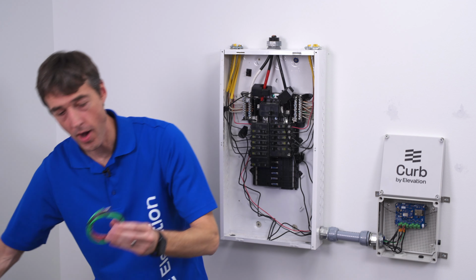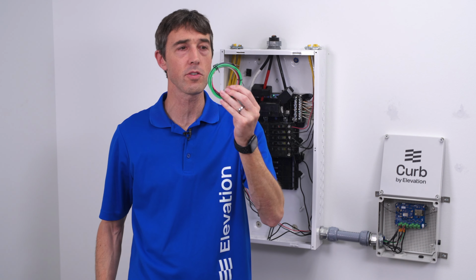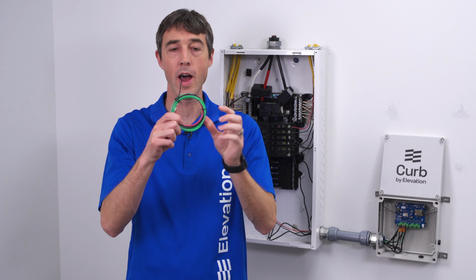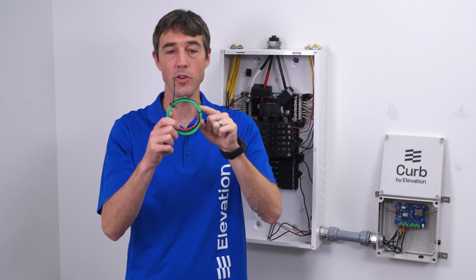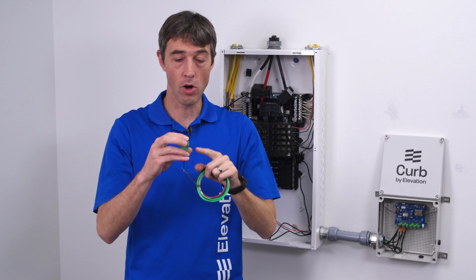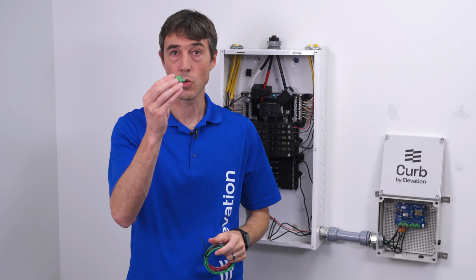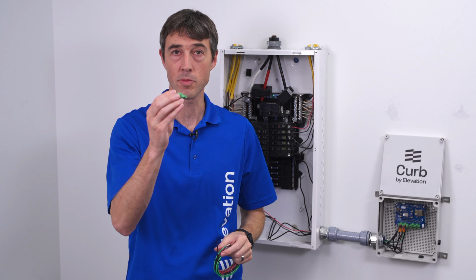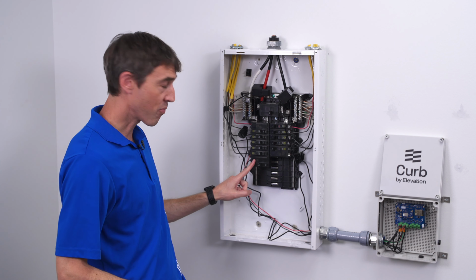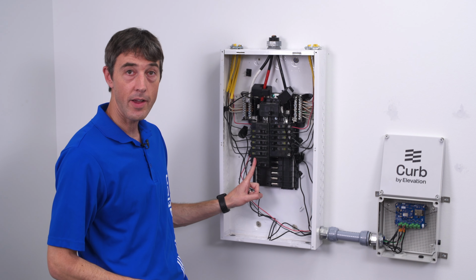Now, the Curb device gets power from 4 individual wires. Here we have a wire for line 1, line 2, a neutral, and a ground. Those all go into the connector block, which then gets plugged into the Curb device. Curb is powered by a separate 20 amp breaker that is installed inside the home's electrical panel.